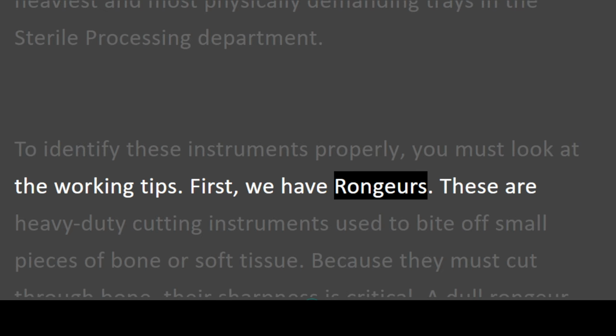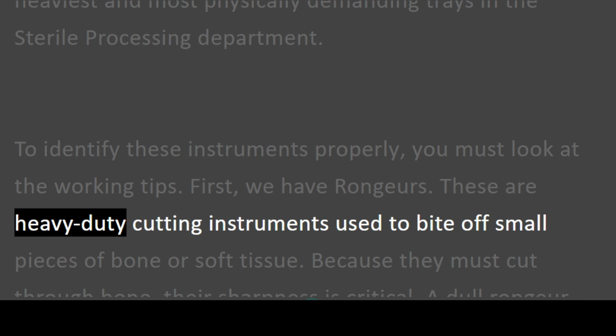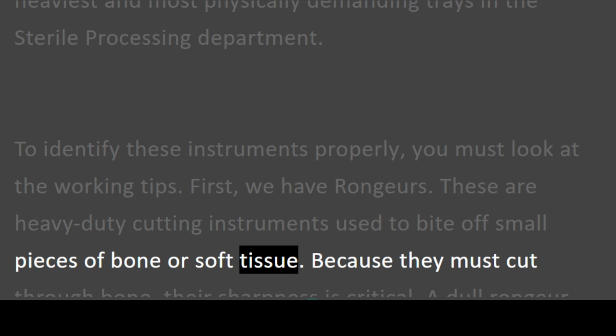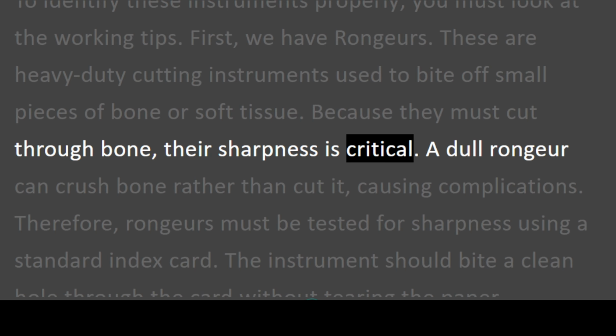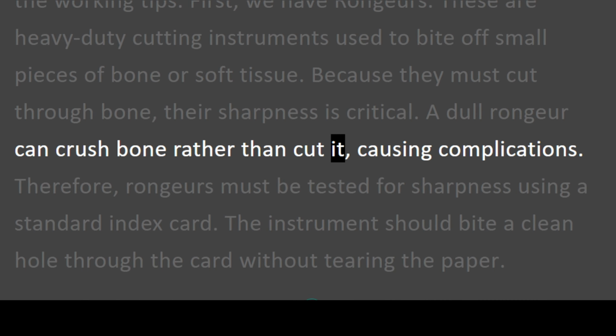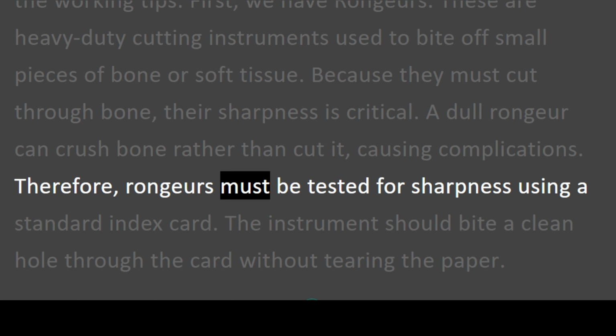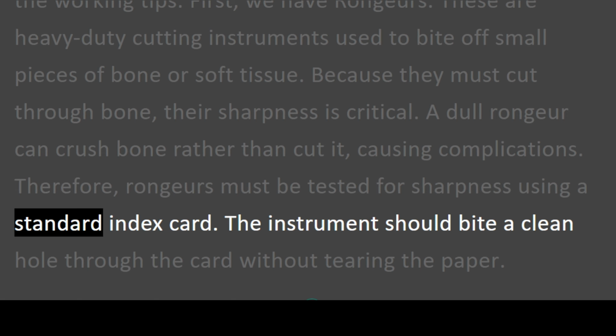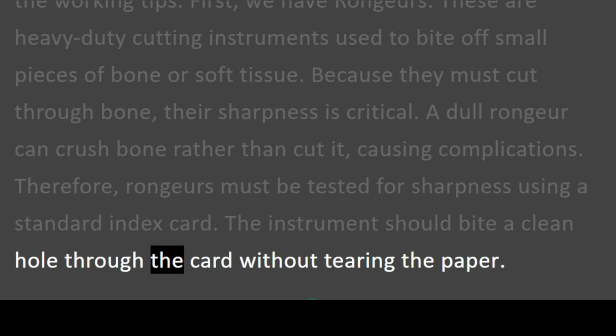First, we have rongeurs. These are heavy-duty cutting instruments used to bite off small pieces of bone or soft tissue. Because they must cut through bone, their sharpness is critical. A dull rongeur can crush bone rather than cut it, causing complications. Therefore, rongeurs must be tested for sharpness using a standard index card. The instrument should bite a clean hole through the card without tearing the paper.